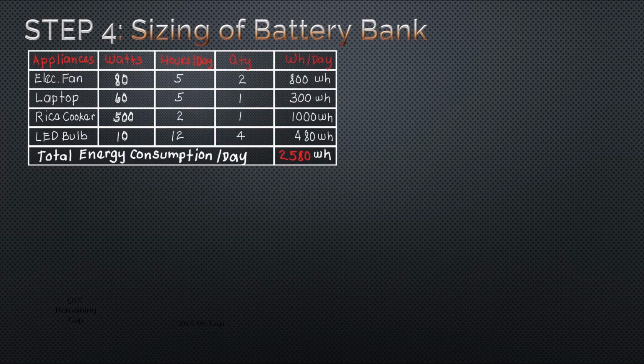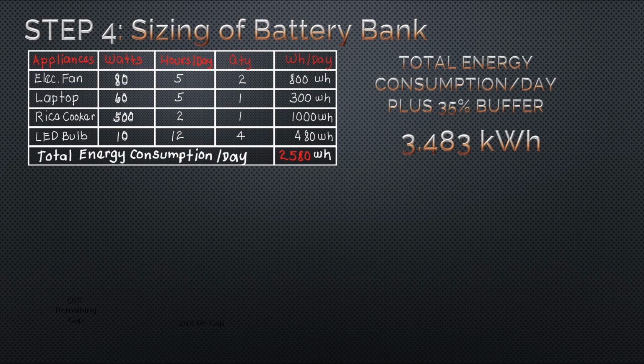So it is necessary to design the rating of battery bank, considering also the parameters we use in sizing the solar panels. So we need to use also the load profile. Now, what are the other parameters we will consider? We will also include a buffer to compensate the system losses, and this is equal to 3.483 kilowatt-hour. This is the total consumption per day plus 35%.